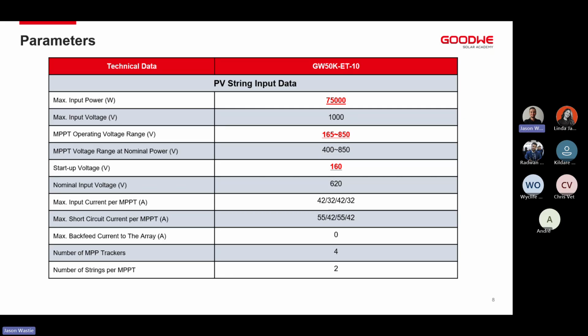Next is the startup voltage of our inverter. So the inverter startup voltage is 160 volts and 165 volts is where we start operating. Note this is a high voltage inverter, it's a 50 kilowatt three-phase inverter. So the operating voltage being as low as it is extremely competitive in the market and something that we definitely do pride ourselves in. This just means that we get extra PV power production during the day or in really bad weather conditions, early in the morning, later in the afternoon, something like that.